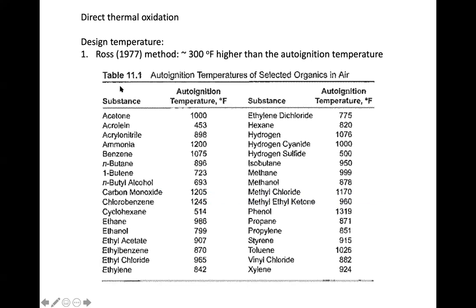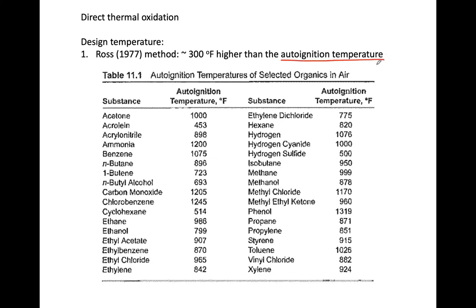Regarding this optimal temperature, there are three ways to calculate it. The first method is called the Ross method. It is defined as 300 degrees Fahrenheit higher than the auto-ignition temperature. The auto-ignition temperature is the temperature at which, if you mix the VOC with oxygen and nitrogen and ramp up the temperature, the VOC will start to ignite and combust automatically.